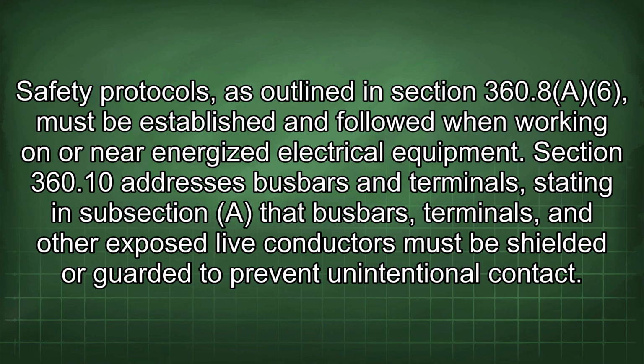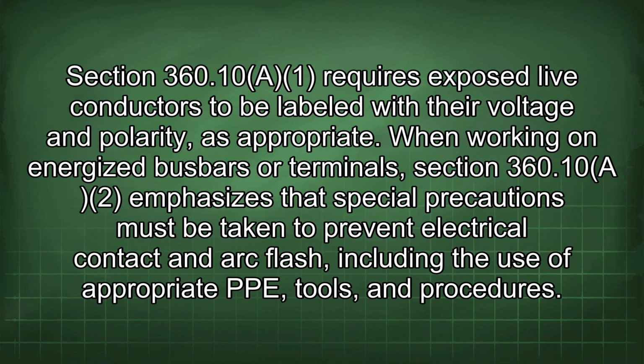Section 360.10 addresses busbars and terminals, stating in subsection A that busbars, terminals, and other exposed live conductors must be shielded or guarded to prevent unintentional contact. Section 360.10A1 requires exposed live conductors to be labeled with their voltage and polarity as appropriate. When working on energized busbars or terminals, Section 360.10A2 emphasizes that special precautions must be taken to prevent electrical contact and arc flash, including the use of appropriate PPE, tools and procedures.